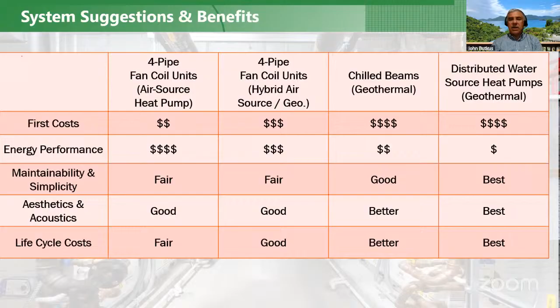So as part of the life cycle cost analysis, with a difference in system costs, we're going to put a square foot cost to each of these four options. If a normal fossil-fueled heating system would require a generator for all the other generator necessities, that's $100,000. How expensive is the generator needed to run an all-electric building in order to freeze-proof it? We would look to run the DOAS, run the DOAS at heat, and keep the building above freezing temperature with just the DOAS, and then only run the DOAS itself and the central system.